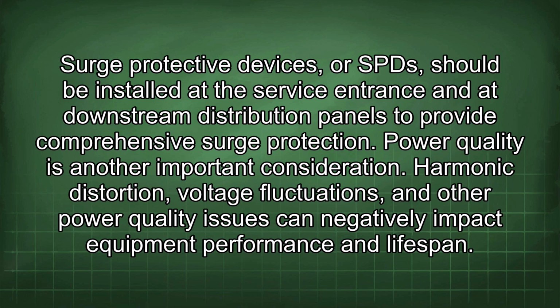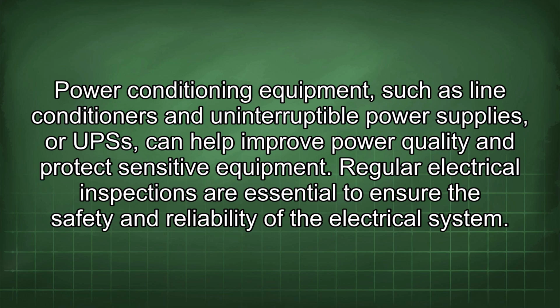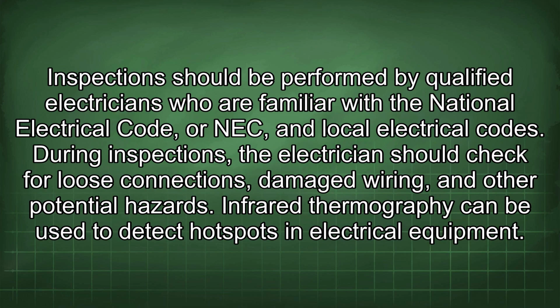Harmonic distortion, voltage fluctuations, and other power quality issues can negatively impact equipment performance and lifespan. Power conditioning equipment, such as line conditioners and uninterruptible power supplies, or UPSs, can help improve power quality and protect sensitive equipment. Regular electrical inspections are essential to ensure the safety and reliability of the electrical system. Inspections should be performed by qualified electricians who are familiar with the National Electrical Code, or NEC, and local electrical codes. During inspections, the electrician should check for loose connections, damaged wiring, and other potential hazards.